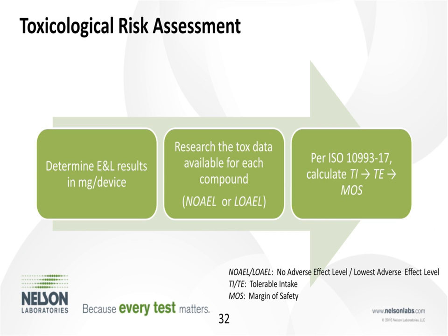And then once you identify an appropriate NOAEL, you're going to use ISO 10993-17 to calculate the tolerable intake, then to calculate a tolerable exposure, and then to finally calculate a margin of safety for the device and the compound of interest. And I'll go into those in more detail now.